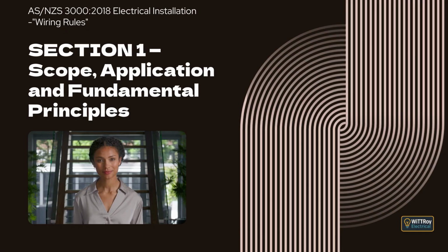In this clause, we talk about what happens when a fault makes metal parts become live. If that happens, a person touching the metal could get a shock, so the standard requires us to put protection in place. The idea is very simple: if a fault can make something dangerous, the installation must have a method that keeps people safe. Every part of the installation must use a method that suits the equipment and the surrounding conditions.